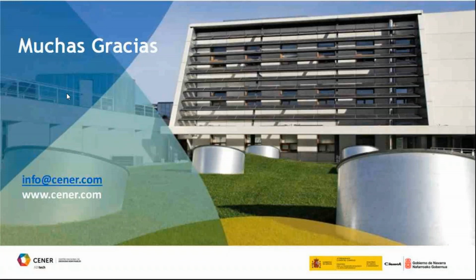Okay. Another question from Antoine. Which tests bring the highest number of failures? In general, from our experience, we have seen that the tests with humidity are the most complex for PV modules to pass.